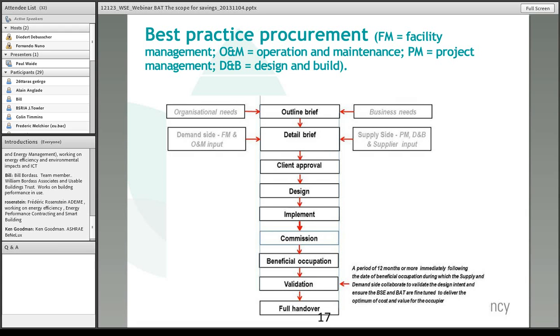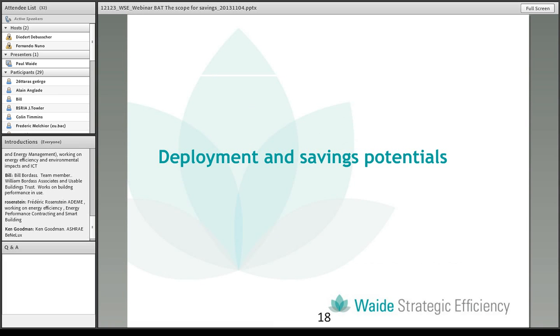The onset of beneficial occupation, i.e. the building is actually being used for its intended purpose, is followed by a period of at least 12 months during which the supply and demand side collaborate to validate the design intent, ensuring the building services engineering and automated technology are fine-tuned to deliver optimum cost and value for the occupier. Ideally, full handover would happen after that period, with confidence that the design intent is actually being achieved in practice. But of course, this best practice procurement suggestion is not what occurs in a great many circumstances in practice.